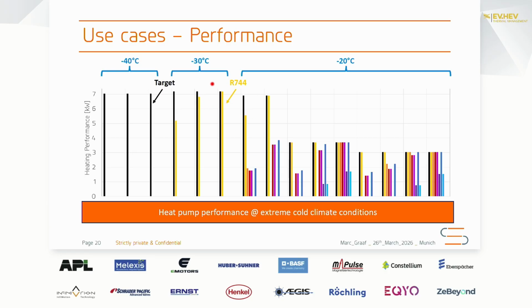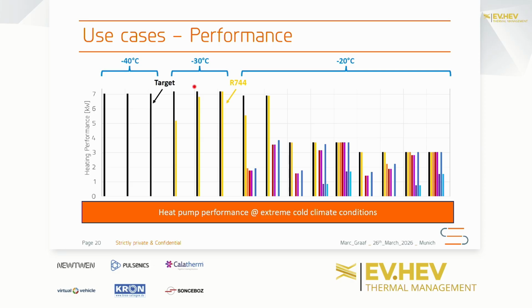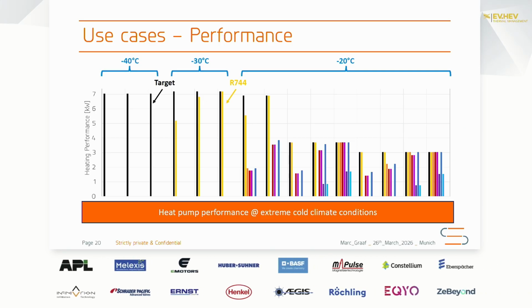At -30 degrees, it already looks a little bit different. We have a CO2 system that is able, in steady state, to achieve the total required heating performance under those conditions without any additional electrical heating. Not in the cold start, of course, where the required condition is not met, so either you take longer to heat up or you need to precondition, but in steady state you would be able to deal with it with the CO2 system alone. If you look at the other heat pumps at -20 degrees, other heat pumps with YF as a refrigerant start working, but not all achieve the required heating performance. So this gap between these systems and the target of the black curve would need to be compensated by electrical heating.